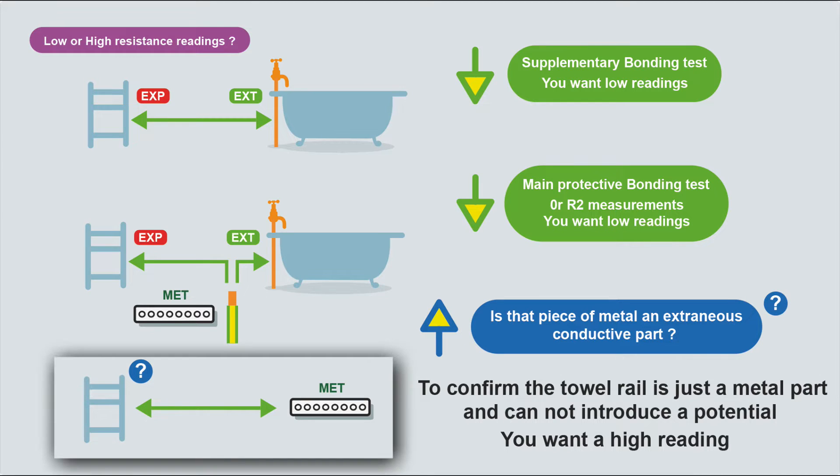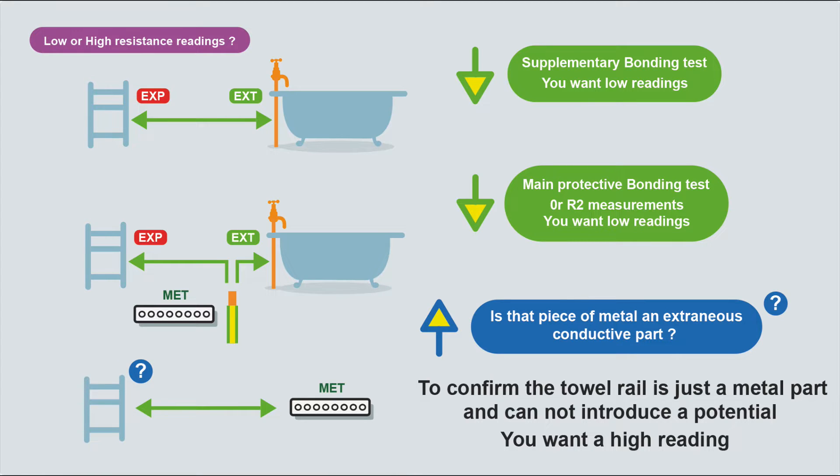We want high resistance if you want to prove that something is not an extraneous conductive part. We want to know that there's no connection to earth, so we want a high resistance reading between that part and the MET.